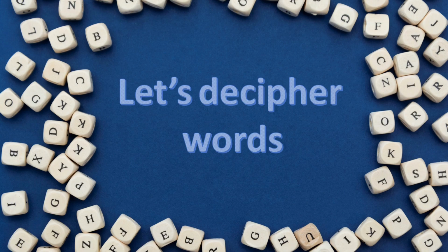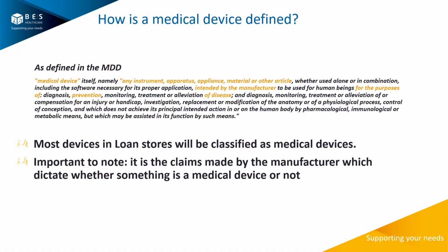There are a number of really fine detailed pieces to these regulations, and it's all down in the wording. So I'm going to bring out a little bit of that here and try to give you a sense of what it's trying to cover. So how is a medical device defined in the first place? I've taken out from the regulation here a piece of the text. There is more to it than this, and there's a lot of fine detail as to how things are worded. But at the end of the day, most of the devices that a loan store is reprocessing are classified as medical devices. And the regulation does say that anything that is used for the cleaning and disinfection of medical devices is also a medical device, and that's really the main point I'm trying to make here. But it's really important to note that whether something's a medical device or not really comes from what a manufacturer claims of their device, and we're going to cover that a few times through this presentation as it is very important.